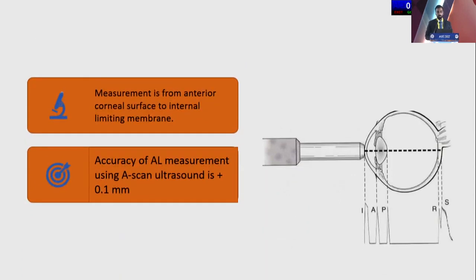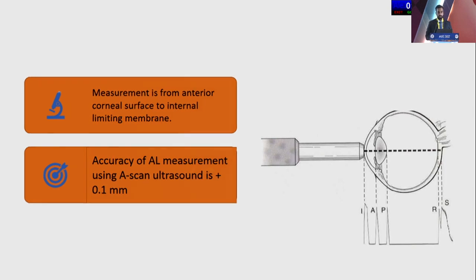The measurement in optical or ultrasonic biometers is usually from the anterior corneal surface to the internal limiting membrane. The accuracy of the ultrasonic biometers is about 0.1 mm between every reading. So a good ultrasonic biometric measurement has to give you these 5 waves. The first one is when the probe meets the cornea. The second wave is from the anterior part of the lens capsule. The third wave is from the posterior pole. Then the fourth wave is from the retina, and the following waves are from the sclera and the orbital fat.